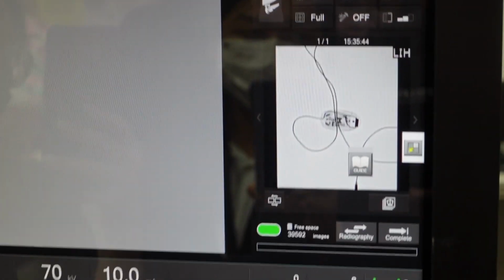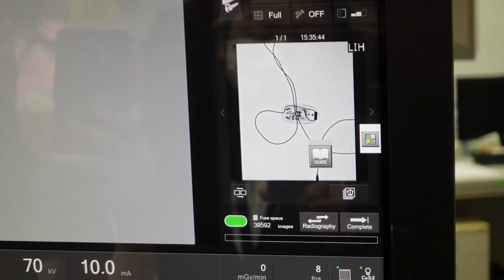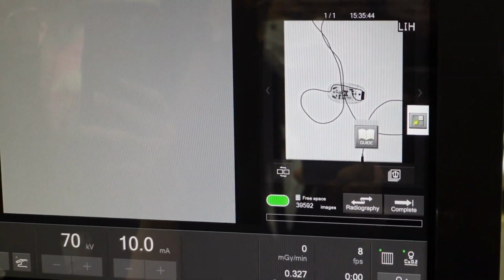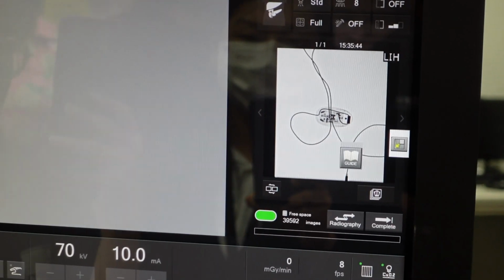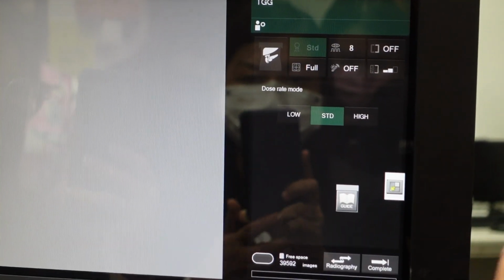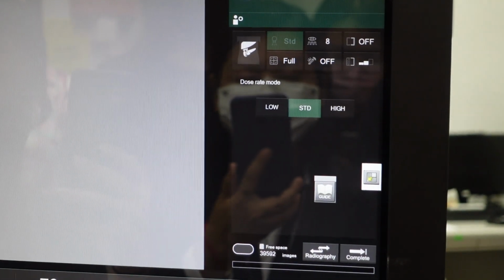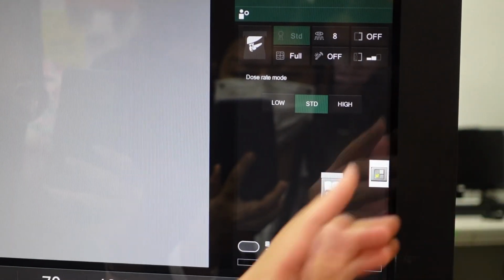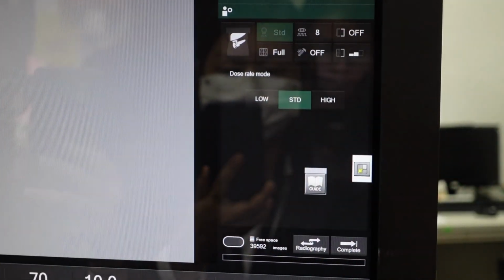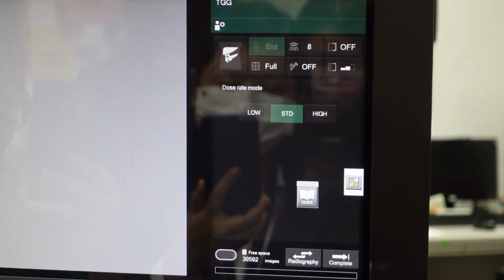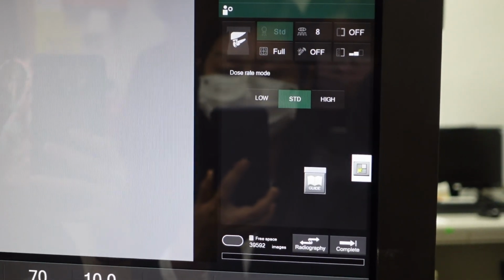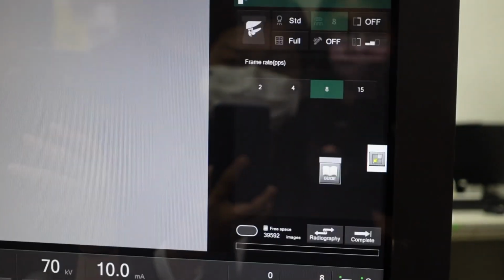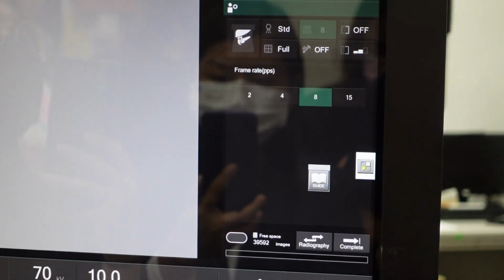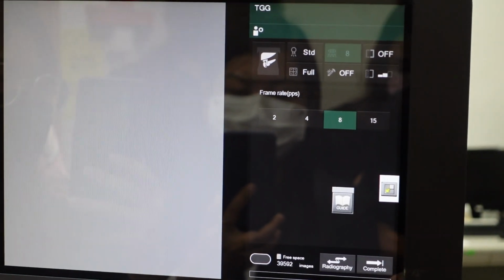Another thing, even though it has this anatomical program, you cannot preset the exposure condition for fluoro. Yeah. So basically, whatever is given by the machine, that is the exposure. Alright. You can't preset. You can only set. You can't even preset anything like how many frame per second, dose rate, whatever. You can't. So this is the dose rate mode. Low, of course, it's low. Now, when they say dose rate, right, what we've seen, they're only altering the kV, right? So high is high, right? Standard and low, right? Now this is the frame rate. Okay, pulse per second, like frame rate, PPS stands for.